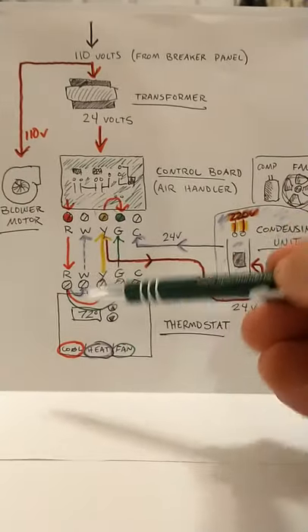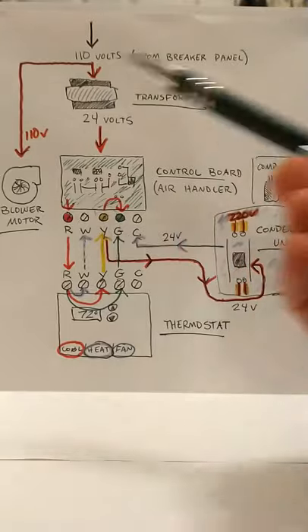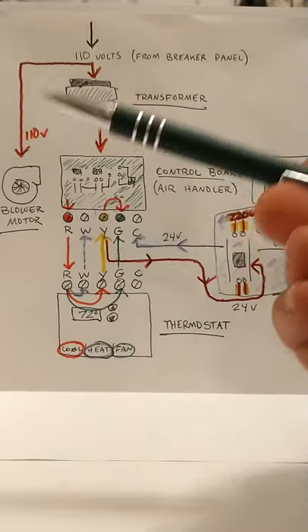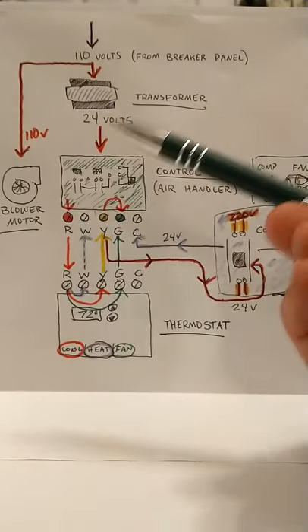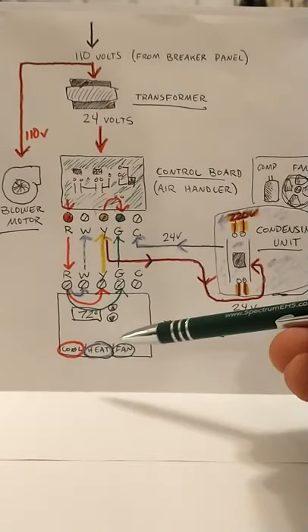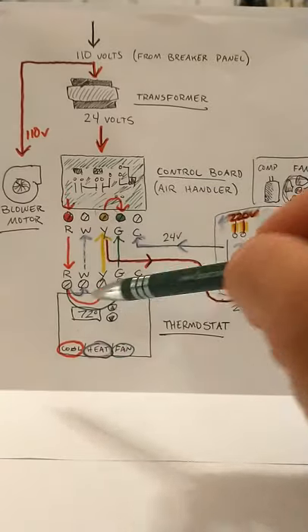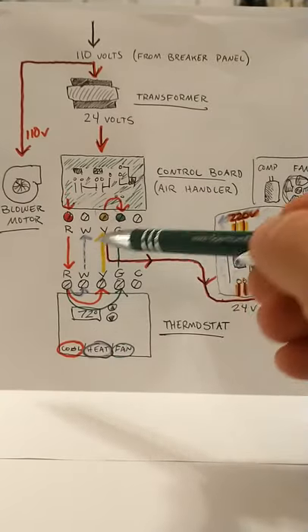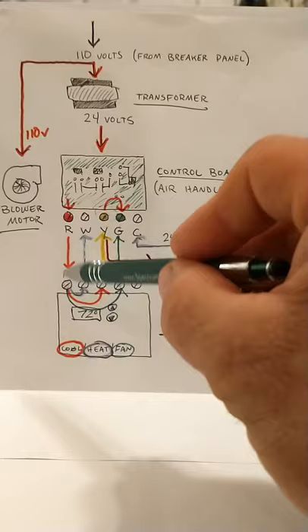If you're running a combined heating and air system, like you have a furnace with an evaporator coil sitting on top of it with a condensing unit outside, and you're just running one thermostat to run that system, you'll often, some thermostats will come with a jumper between that RC and that RH.